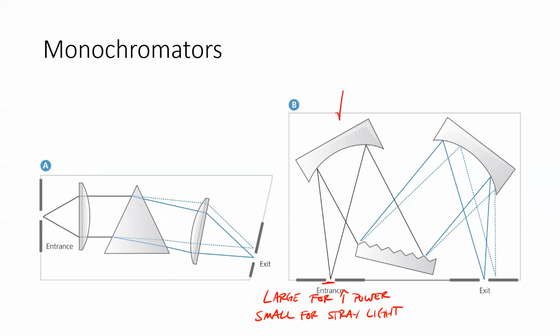Right, so we go to this first mirror. I think I said it on Friday, but this is a collimating mirror. Remember, collimating is where we get all of our waves going in the same direction. Dispersed is what's happening here, where as we go away from that entrance slit, they spread out. The collimating mirror means that they travel in a straight line. They don't diverge. And so we have that collimating mirror to our diffraction grating.